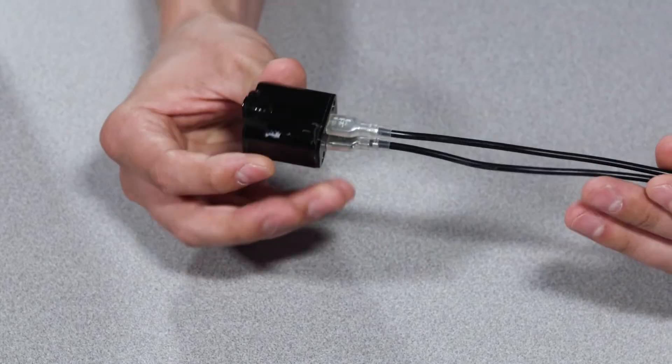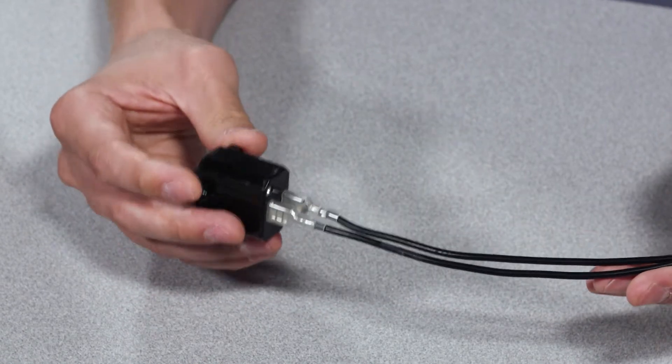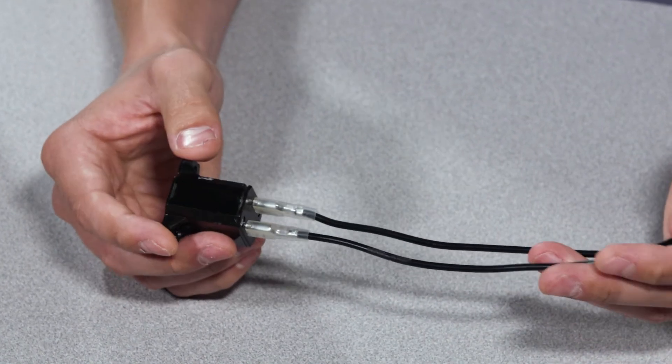If you find one of these parts bad or open with an ohmmeter, you want to replace it with a PTCR and not a traditional hard start kit.